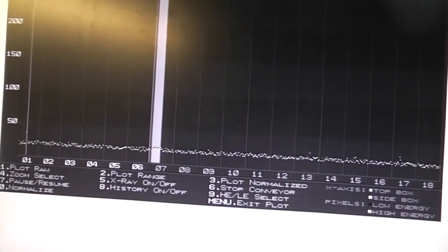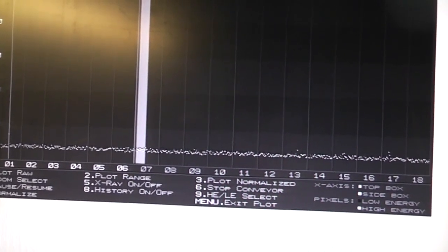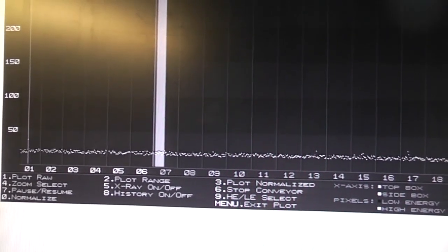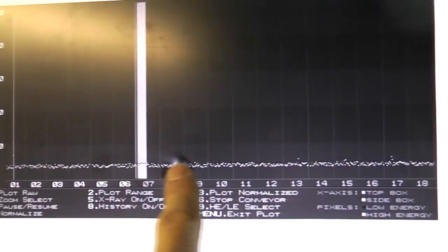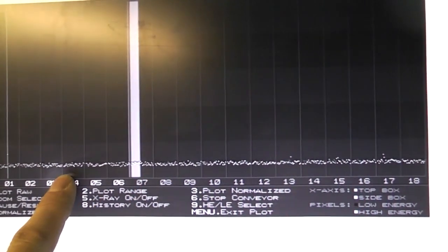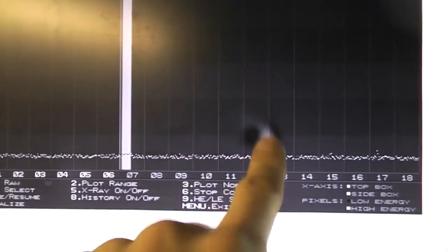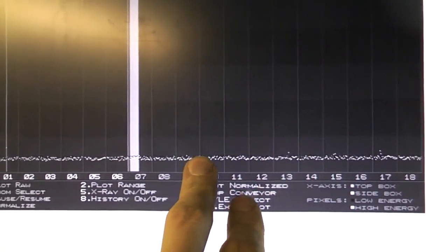Judging by the way this behaves, I'm fairly sure that this is reading something on startup that's then being stored and then used to control the data, whether it's some sort of additional calibration above the normalisation or whether it's the normalisation data, I'm not sure. We've still got this marker here, but we've got a very, very level set of data now. So I just wonder if maybe all that rubbish was a bad connection on that analog cable, and just me disturbing it has perhaps fixed that.